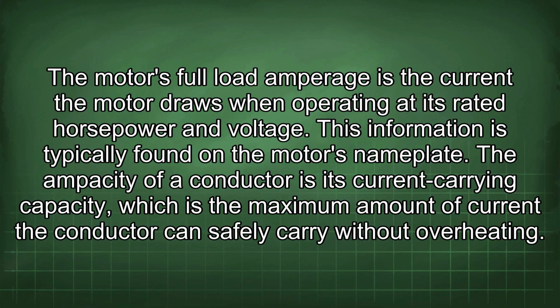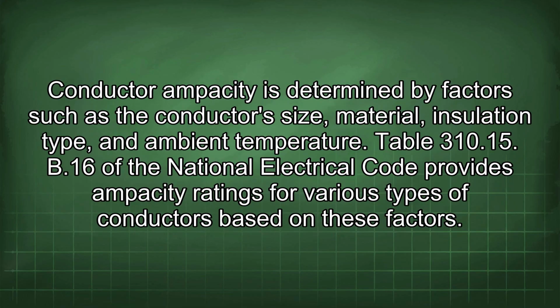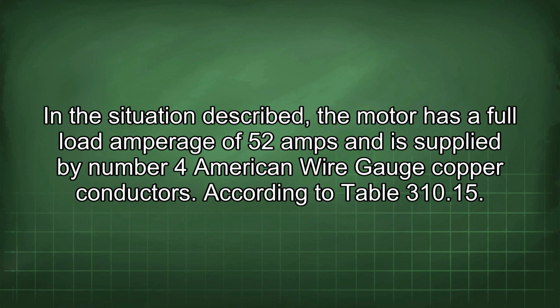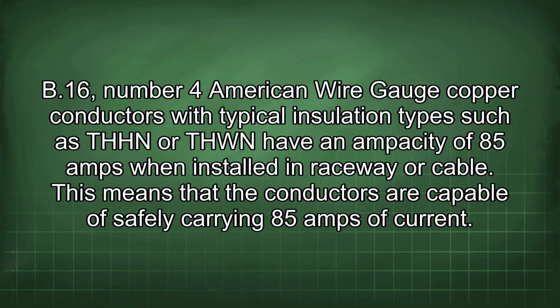The ampacity of a conductor is its current carrying capacity, which is the maximum amount of current the conductor can safely carry without overheating. Conductor ampacity is determined by factors such as the conductor's size, material, insulation type, and ambient temperature. Table 310.15(B)(16) of the National Electrical Code provides ampacity ratings for various types of conductors based on these factors. In the situation described, the motor has a full load amperage of 52 amps and is supplied by number 4 American wire gauge copper conductors. According to Table 310.15(B)(16), number 4 American wire gauge copper conductors with typical insulation types such as THHN or THWN have an ampacity of 85 amps when installed in raceway or cable. This means that the conductors are capable of safely carrying 85 amps of current.